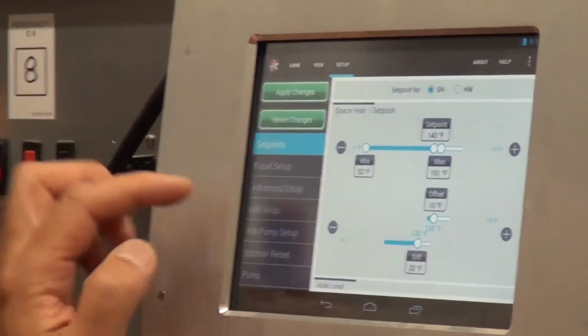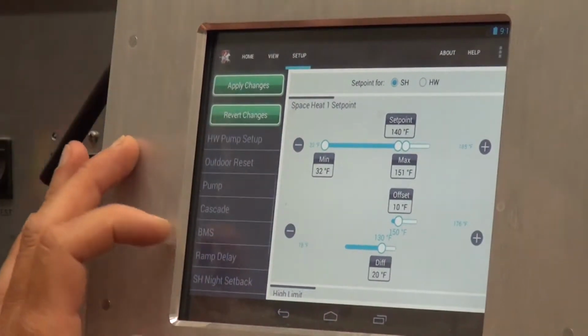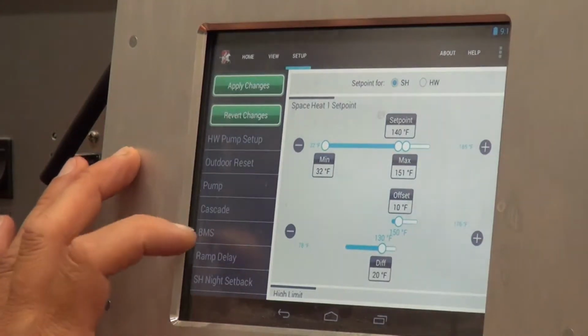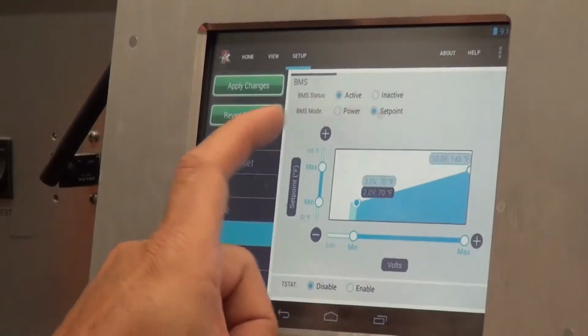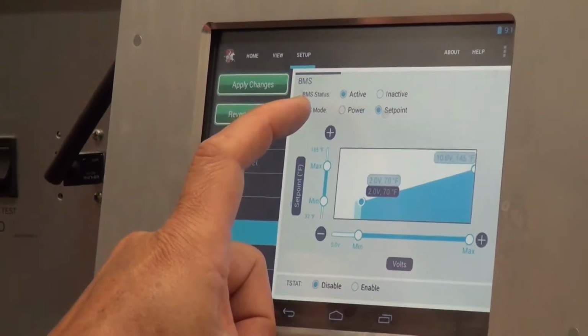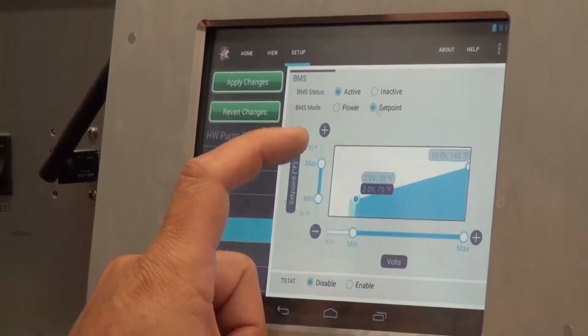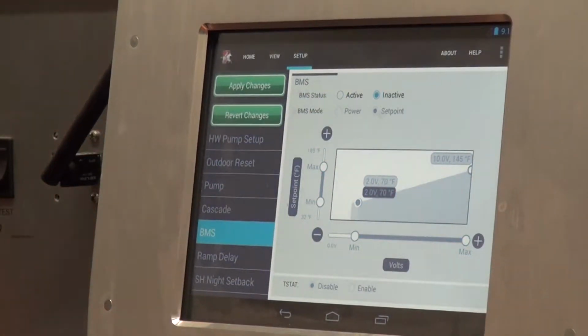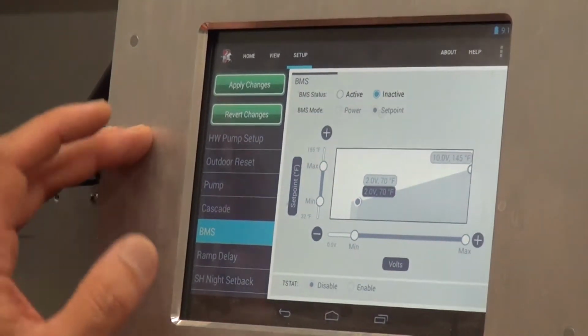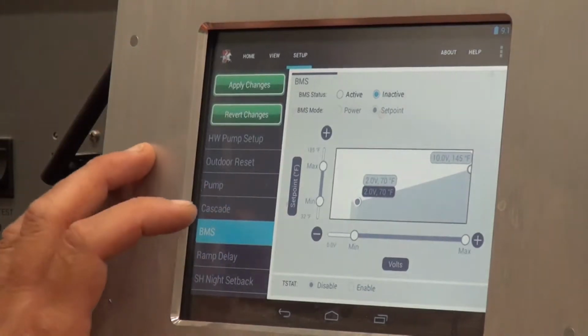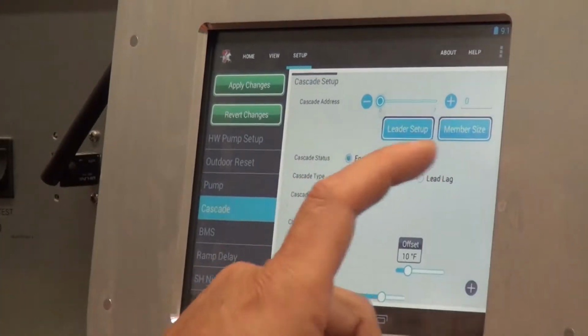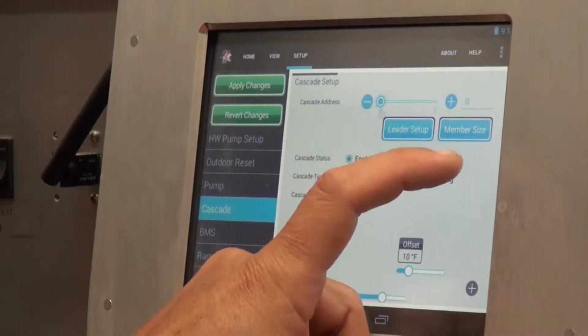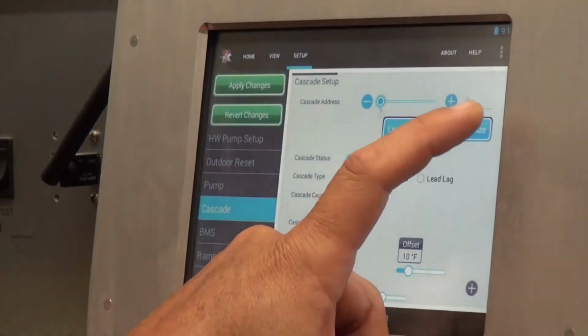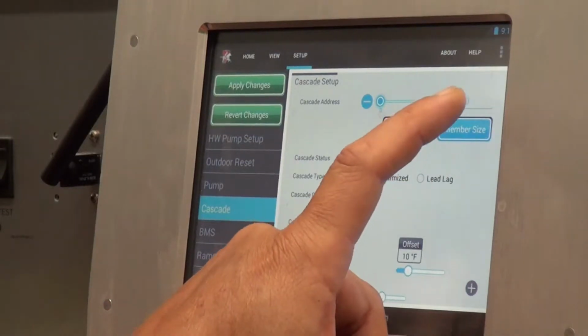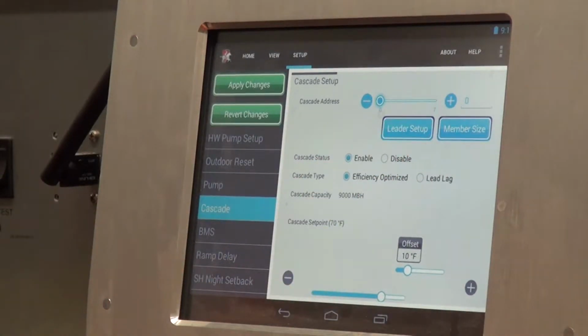you have to get into the setup. BMS stands for Building Management System. That means the energy management system has control over it. We have to deactivate it so it's not taking control over the boiler anymore. You actually have to go into the cascade position and we can leave this one out, and then you can go to this one and turn it to boiler number 1.